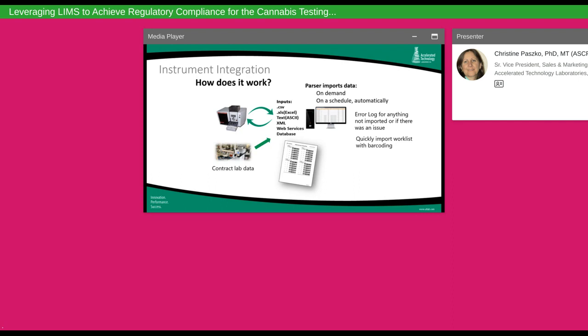Let's discuss instrument integration and how it works. Instruments output data in a number of different formats: CSV, XLS, text or ASCII, XML, and others. Those formats are typically unique based on how the owner has set up the instrument, so each instrument requires a unique parser to import data into the LIMS. Once data has been electronically moved into the system, there's no need for hand entry — all that's required is a review and approval. Clients can also take data from subcontracting labs and create a parser for automatic import.